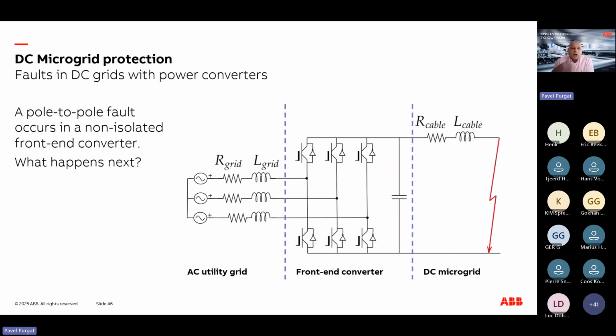Another aspect is, how do we evaluate the short circuit on the output of the converter? And this is based, of course, on the standard, but we need to be careful in evaluating the right impedances. So the cable resistance and inductance, or the busbar resistance and inductance.